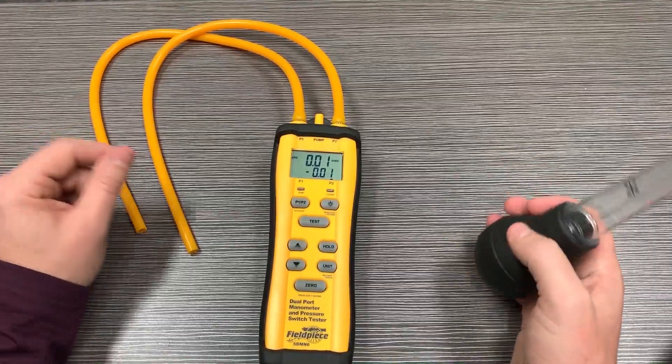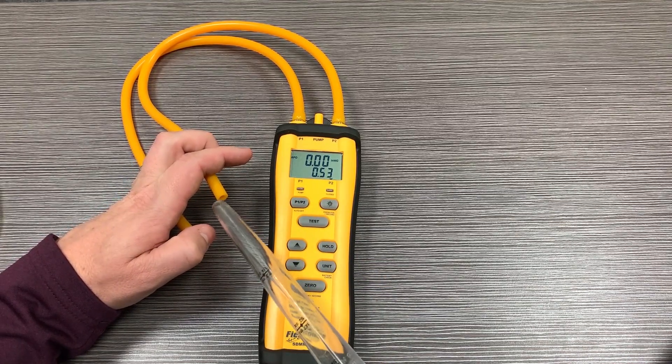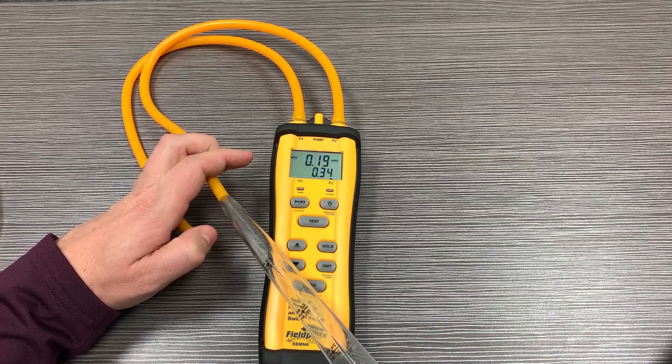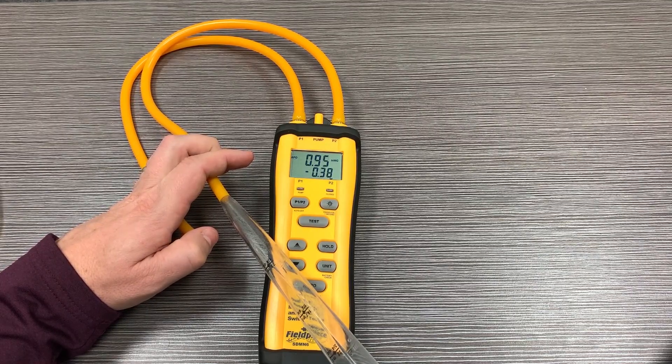Now if we wanted to do something a little bit more complicated, I'm going to trap a little bit of positive pressure in that P2. Now if I affect P1, we're going to see the delta, the difference between the two, on the bottom, and the absolute pressure on P2 represented on top.